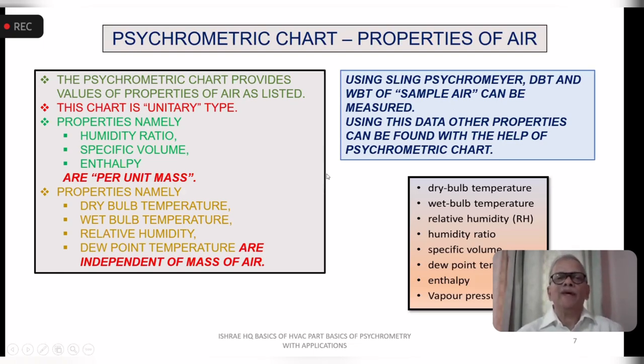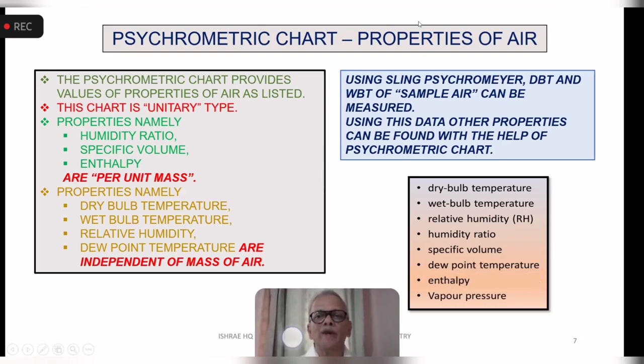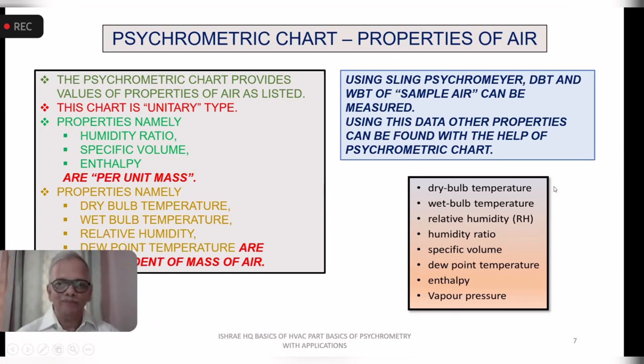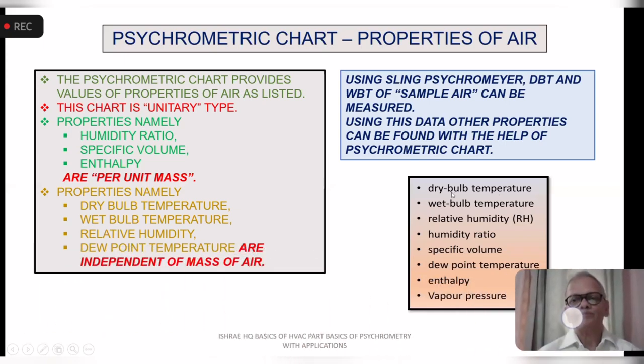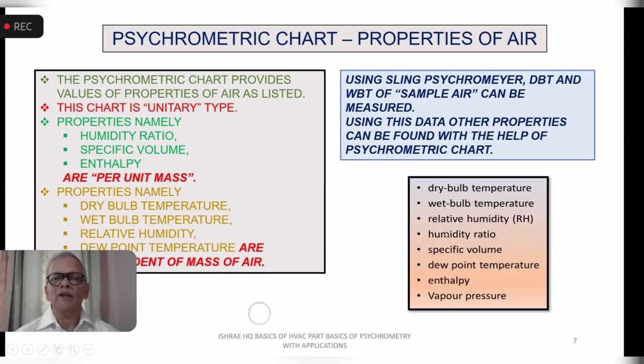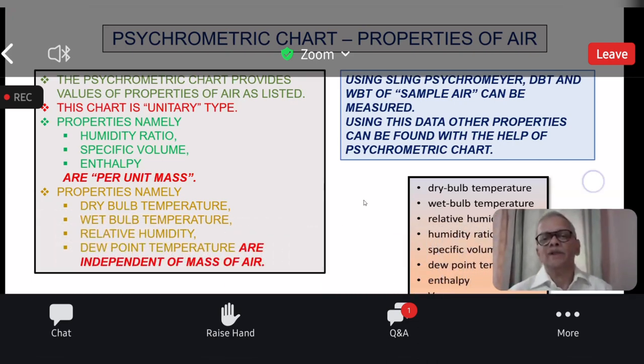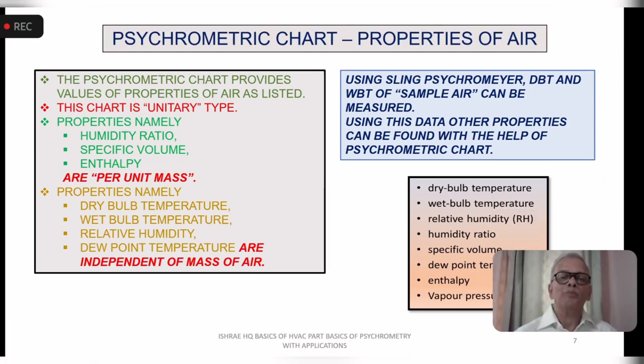Now, this is an important slide, I would say, because when we are talking about properties of air, we have seen in the previous slide what properties we are looking at: dry bulb, wet bulb temperature, relative humidity, humidity ratio, specific volume, dew point temperature, enthalpy, and vapor pressure. In this, what we do not see is the absolute humidity, which is in terms of grains or grams per cubic feet or per cubic meter volume. Rarely used, but sometimes the consultants do specify that as a parameter. Now, these are the properties listed. So the psychrometric chart provides values of the properties of air as listed, which are this.